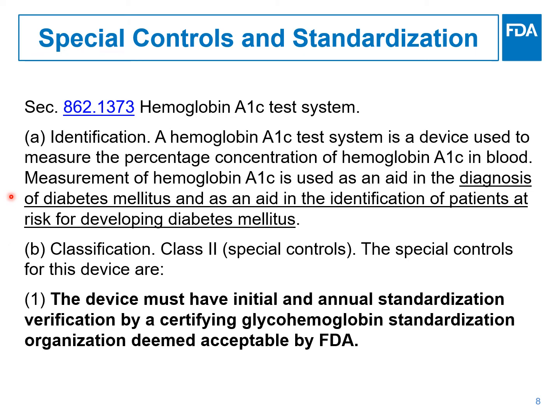Accuracy and precision of such tests are, in part, addressed by the first special control, and this one requires that the device must have initial and annual standardization verification by a certifying glycohemoglobin standardization organization deemed acceptable by FDA. For A1C assays, one example of an organization that has been deemed acceptable is the National Glycohemoglobin Standardization Program.